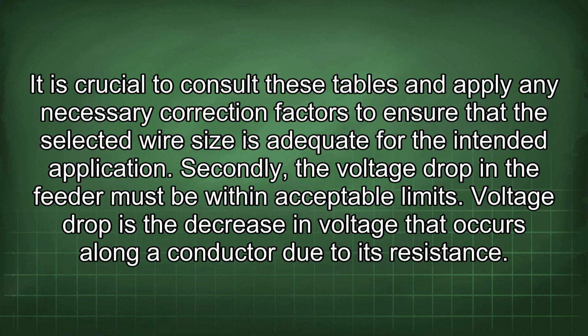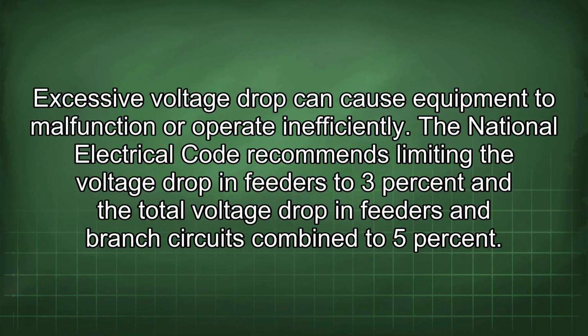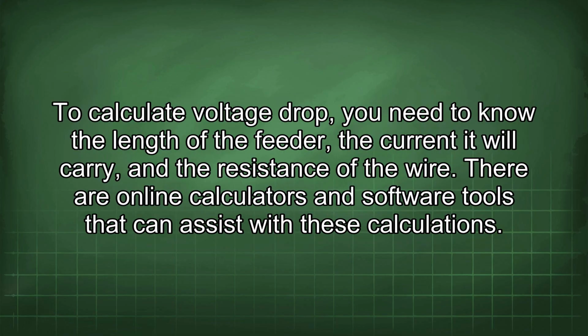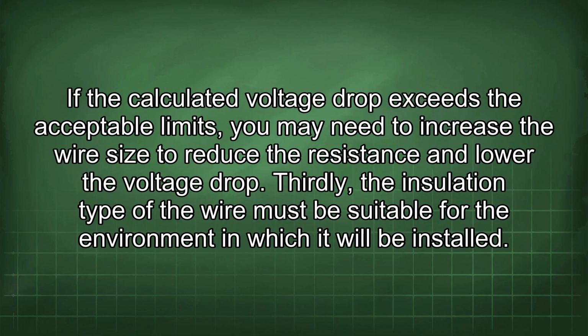Secondly, the voltage drop in the feeder must be within acceptable limits. Voltage drop is the decrease in voltage that occurs along a conductor due to its resistance. Excessive voltage drop can cause equipment to malfunction or operate inefficiently. The National Electrical Code recommends limiting the voltage drop in feeders to 3% and the total voltage drop in feeders and branch circuits combined to 5%. To calculate voltage drop, you need to know the length of the feeder, the current it will carry, and the resistance of the wire. There are online calculators and software tools that can assist with these calculations. If the calculated voltage drop exceeds the acceptable limits, you may need to increase the wire size to reduce the resistance and lower the voltage drop.